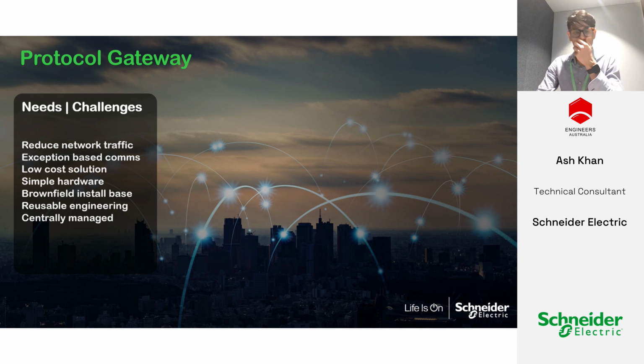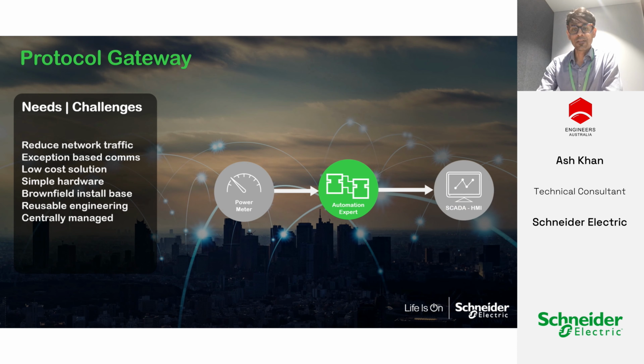Simplified application for protocol gateway, reducing traffic on the network. Previously, the customer had a lot of noise on the network when collecting information from the devices, so they wanted something more modern, like MQTT, more based on exceptions. It's a low-cost solution, simple hardware that can be easily deployed in the brownfield, with reusable engineering that can be reused multiple times and centrally managed. In this case, we're looking at power meters interfacing with the Automation Expert device, and then visualizing on the SCADA and HMI.